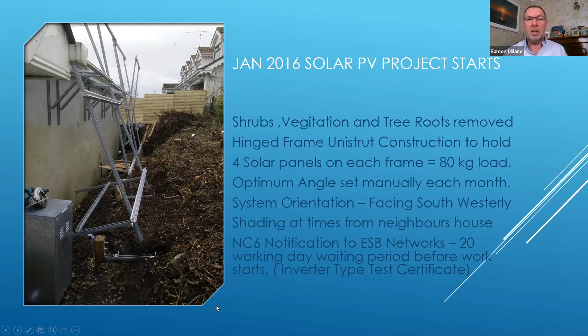At the same time as starting this, there is an NC6 notification to ESB networks. They have a 20-day waiting period for that. And what you're doing is you're sending them data of what you're about to put in, giving them the information in relation to the inverter type, including its type test certificate, to make sure that it's suitable and acceptable for connection to the grid, and that it satisfies all of the grid code.